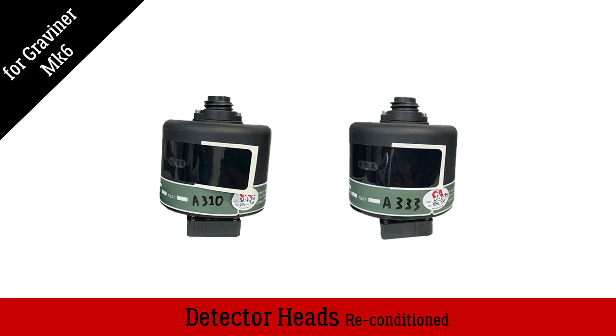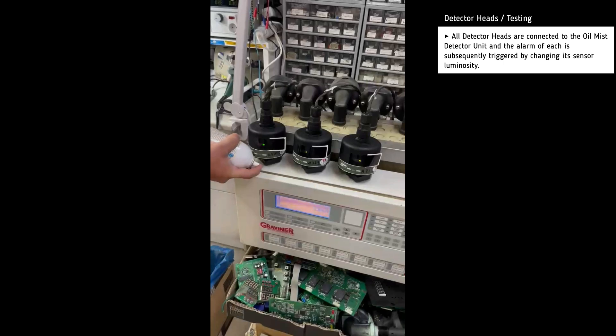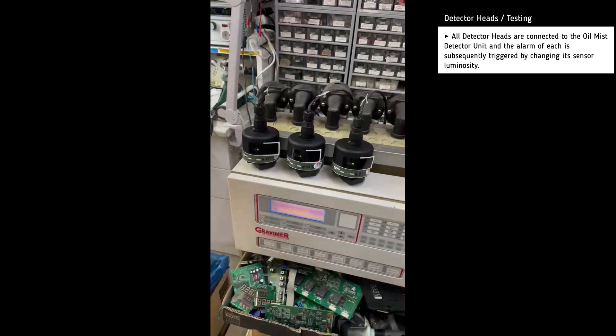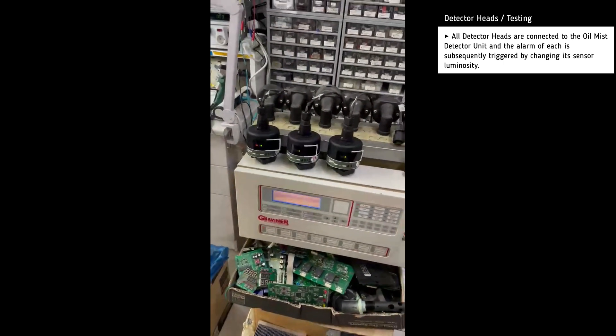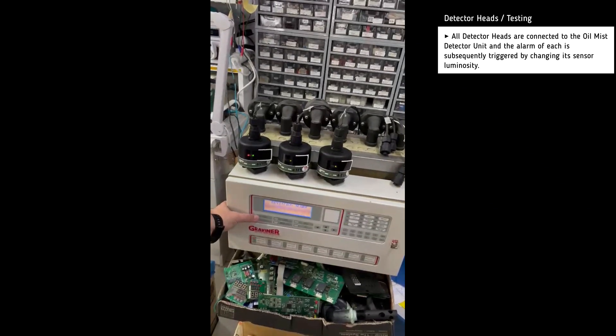Reconditioned heads for the Graviner Mark 6 Oil Mist Detector. For testing, the heads are connected to the unit and then we simulate the oil mist with smoke detector spray, sprayed on a head's path.